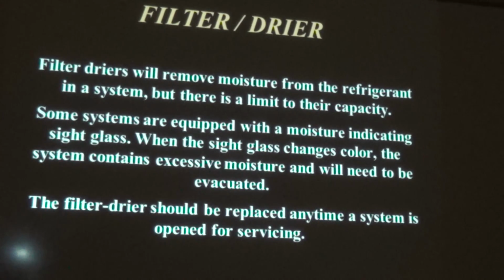Filter dryers, type 2 equipment, usually split air conditioners and heat pumps, usually R22, they love water. So just going back in the past, filter dryers remove moisture from the refrigerant in the system. There is a limit to their capacity. Some of them are equipped with a moisture indicating sight glass. When the sight glass changes color, the system has excessive moisture and needs two things: recover the refrigerant, vacuum and dehydrate the system. And any time you open one of these systems, you should replace the filter dryer.